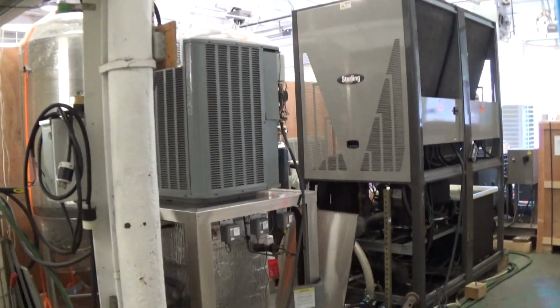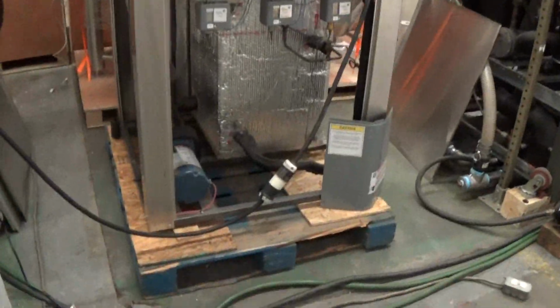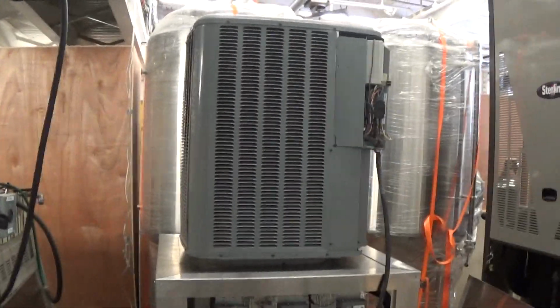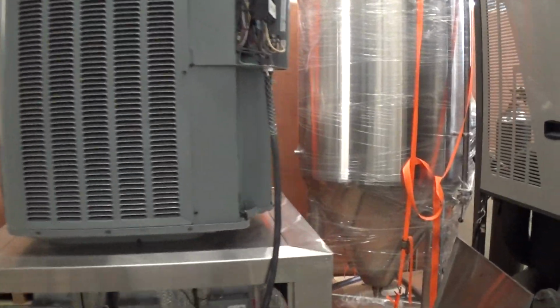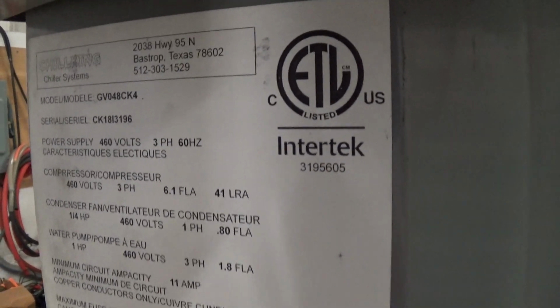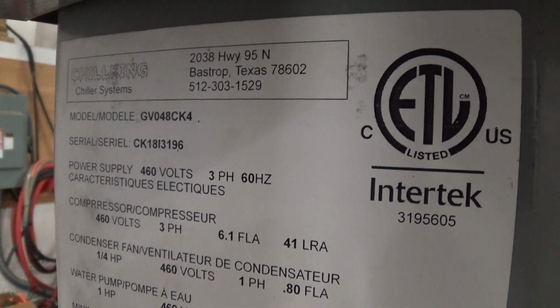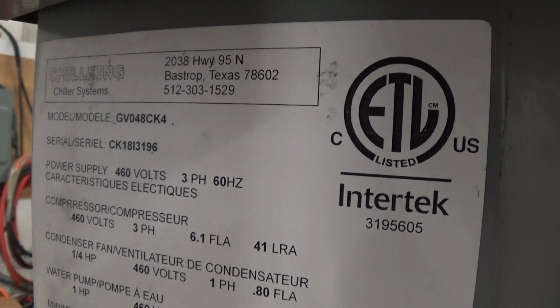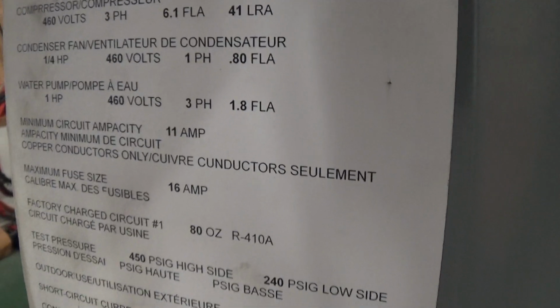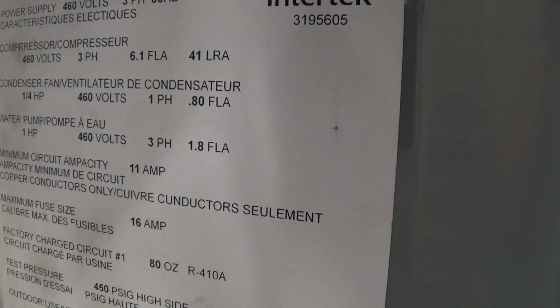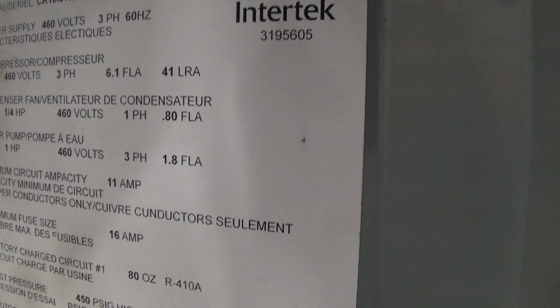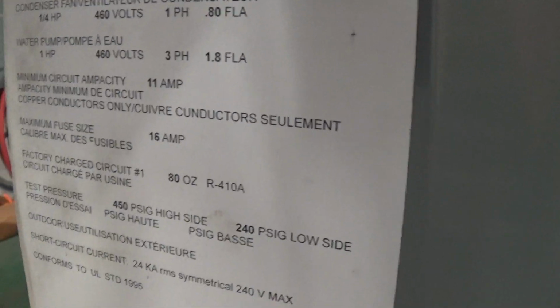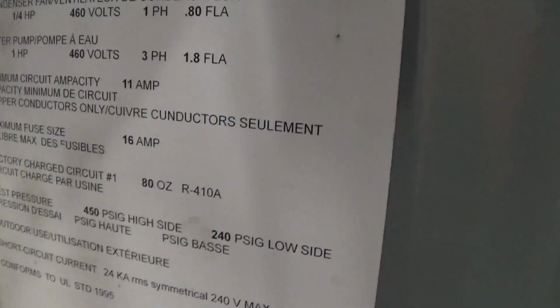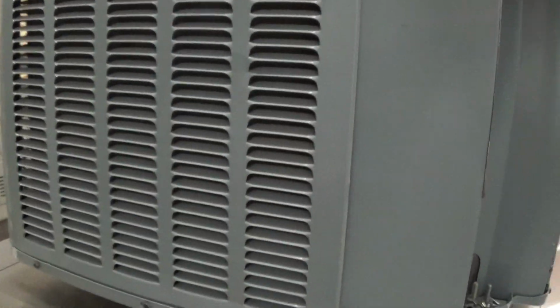It's August 2022. We're going to do a runoff video today of this 4-ton, 460 volt Chill King vertical air-cooled chiller. This is a 460 volt unit, like I said, model GV048CK4, serial number CK18I3196, meaning it's a 2018 unit. It being 460 volt, the pump draws 1.8 amps, and the minimum circuit ampacity is 11, maximum fuse 16. This is an R410A refrigerant machine.